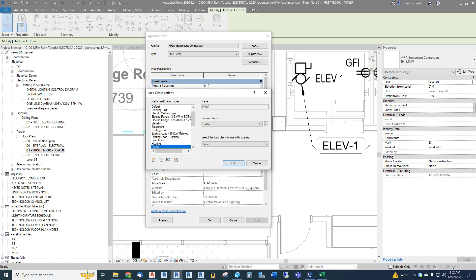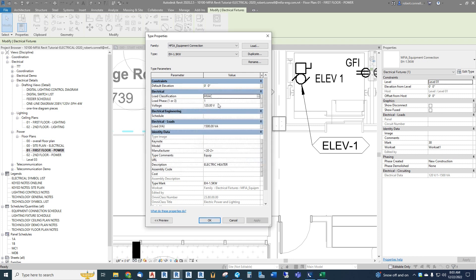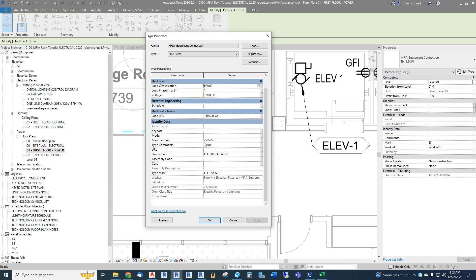There are a bunch of different load classifications you can choose, which helps in load summaries to show the different types of connections, but it also applies the proper demand factor to that piece of equipment. The load is 1500 VA. Now, don't let the labels here confuse you — to build this schedule we used built-in parameters that we repurposed. For example, we don't need to list a manufacturer for this equipment since that's something the mechanical engineers do.